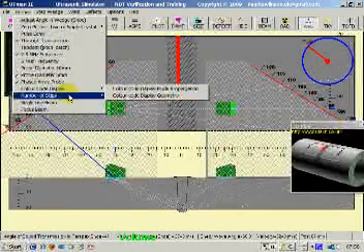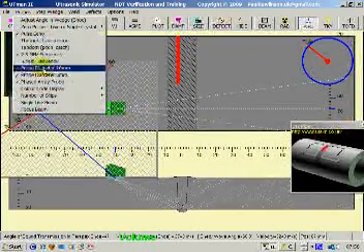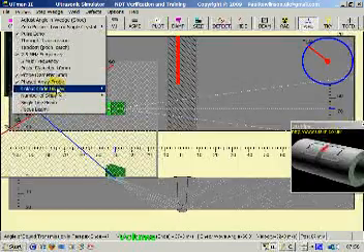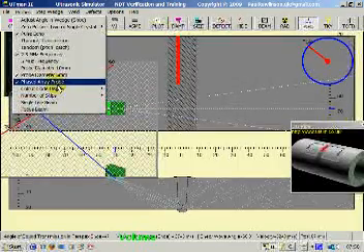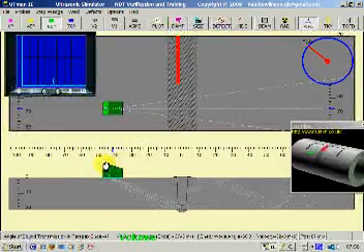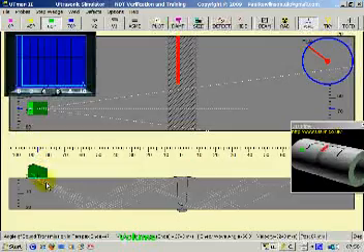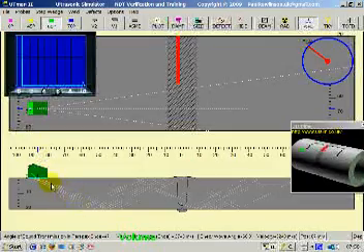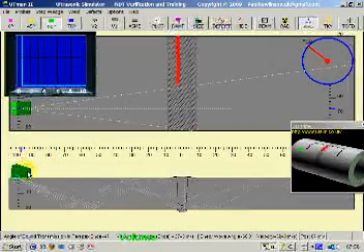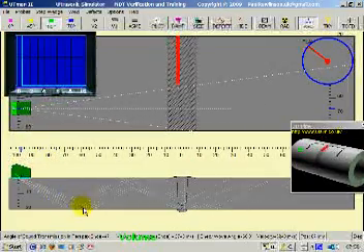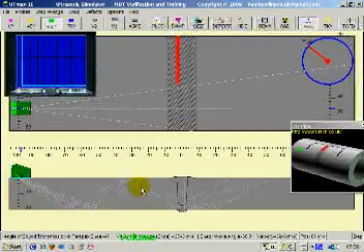We can color code the display for training purposes. And we can increase the number of skips. As I mentioned earlier, skip is the distance the sound travels to hit the back wall and bounce up again. That is a full skip.